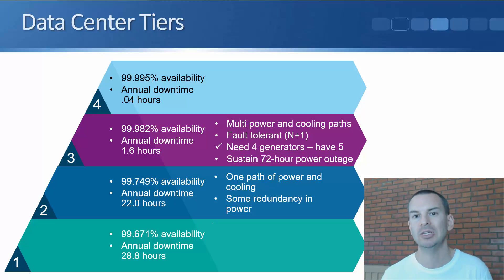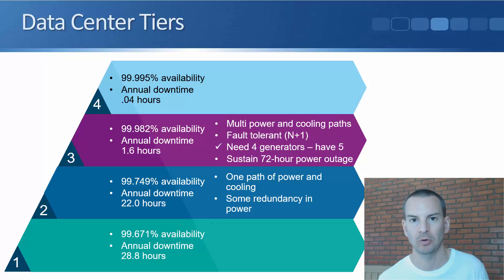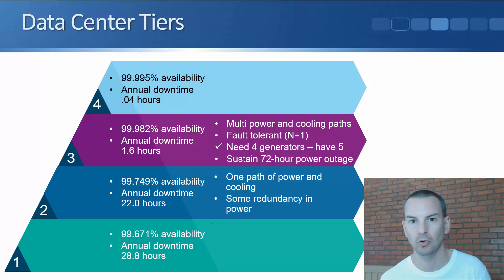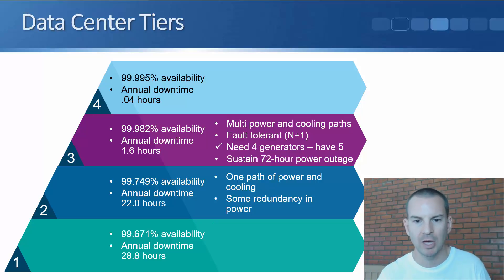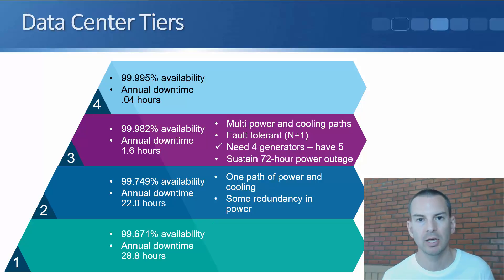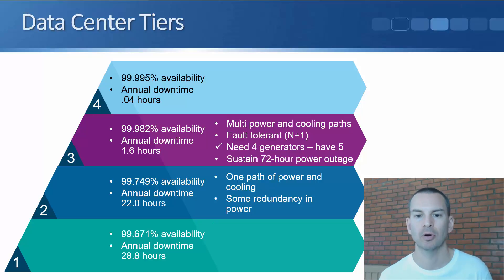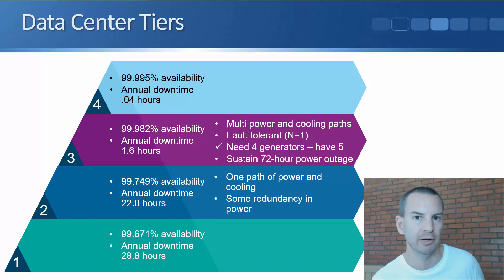Starting at the bottom, a tier one data center is expected to have 99.671% availability, equating to an annual downtime of 28.8 hours, with no requirements for redundancy. A tier two data center requires more availability — only 22 hours of annual downtime — with one path of power and cooling but some redundancy for power components. Moving up, a tier three data center has an annual downtime of only 1.6 hours, requires multiple power and cooling paths, and must support N+1 fault tolerance — for example, if you need four generators, you put in five.